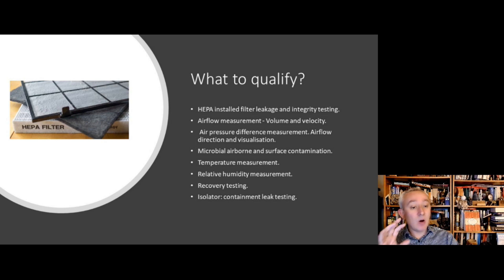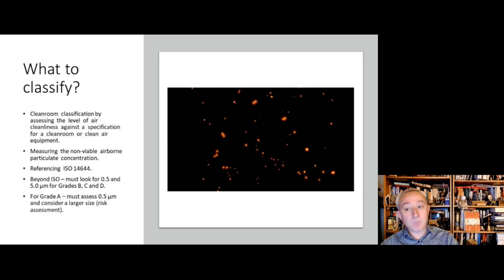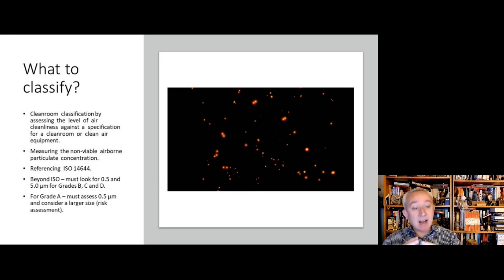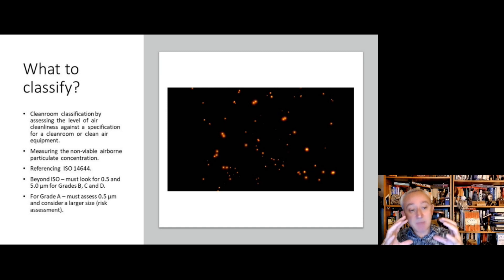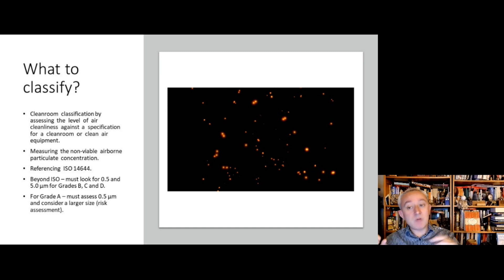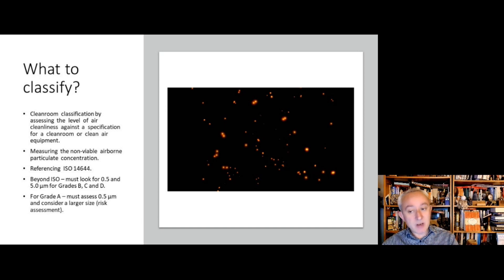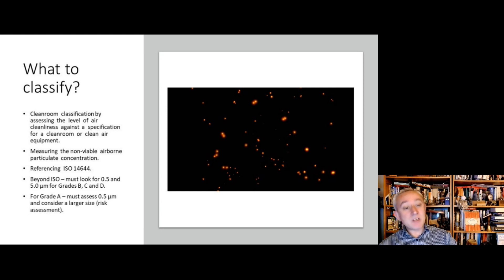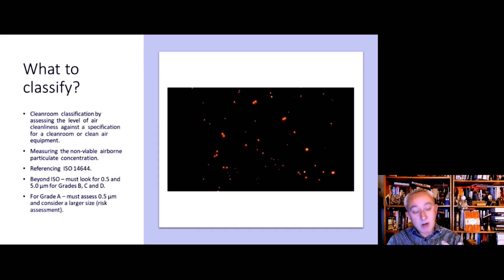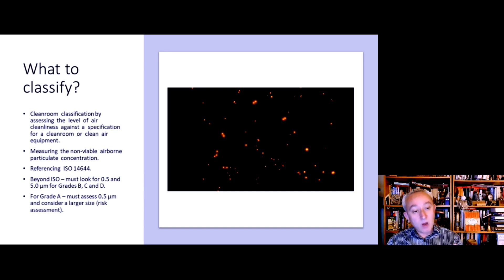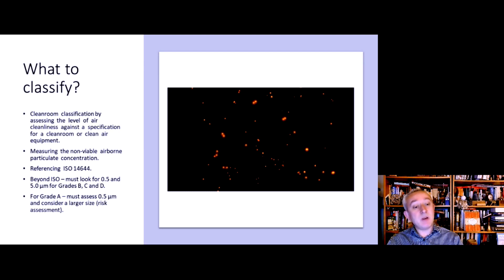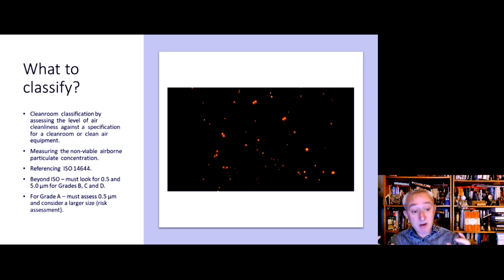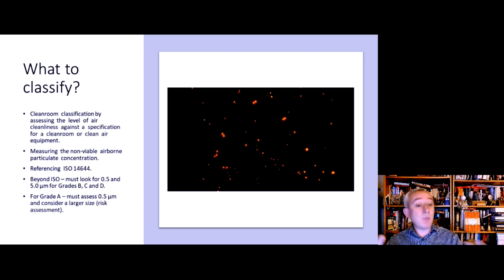In terms of what to classify, clean room classification is based on the air cleanliness, and air cleanliness is defined by the concentration of airborne particulates as measured in a cubic meter of air. So it involves measuring the non-viable airborne particulate concentration. From a previous video, we talk about particulates rather than particles, and all this needs to be conducted—the ISO requires that we classify as 0.5 and greater microns for B, C, and D, but EU GMP Annex 1 says we also need to classify for 5 micron particles as well. For grade A, there needs to be a risk assessment which will form part of the contamination control strategy that says is another particle size other than 0.5 required, such as 1 micron.